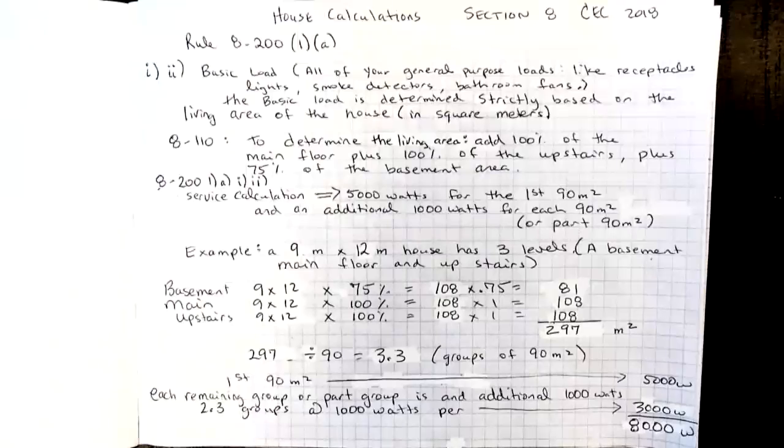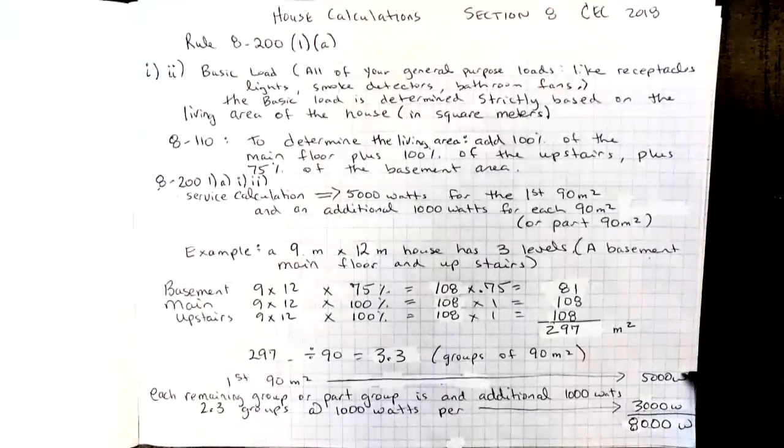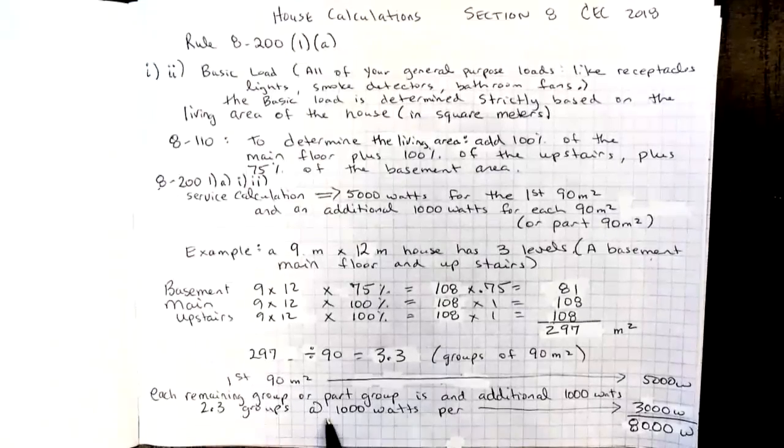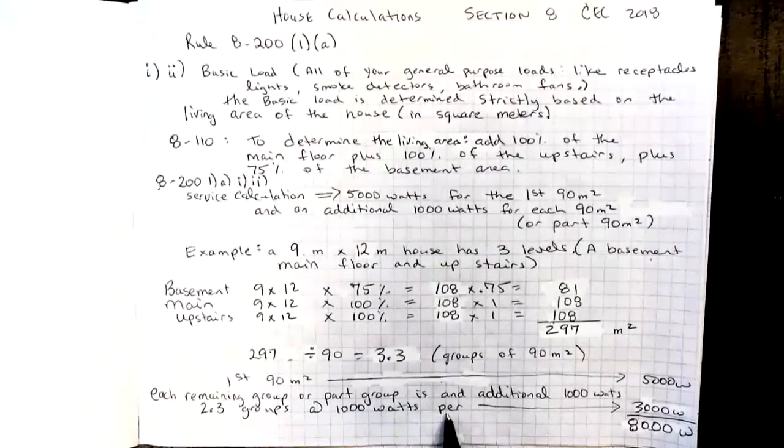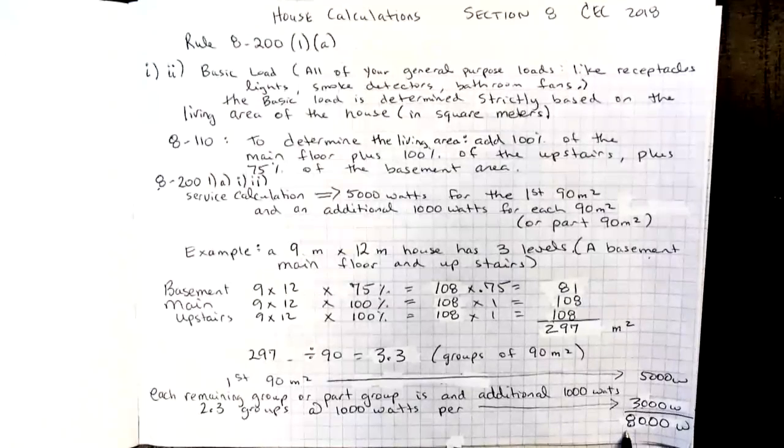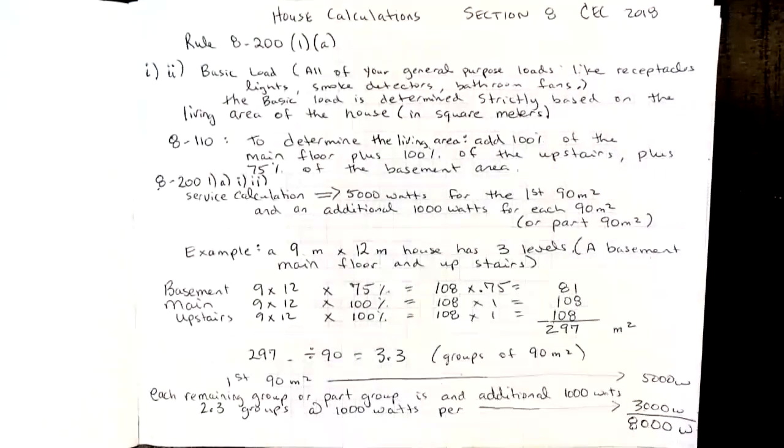To apply the demand factors from 8-200-1A, item one and two, what I would do is then divide 297 by 90. That gives me the groups of 90 meters squared. The first group of 90 meters squared, I'm going to apply 5,000 watts. That leaves me with 2.3 groups left over, and I apply an additional 1,000 watts per group. So that's going to be an additional 3,000 watts. So all together, based on the living area of this home, my basic load is going to calculate out to 8,000 watts.